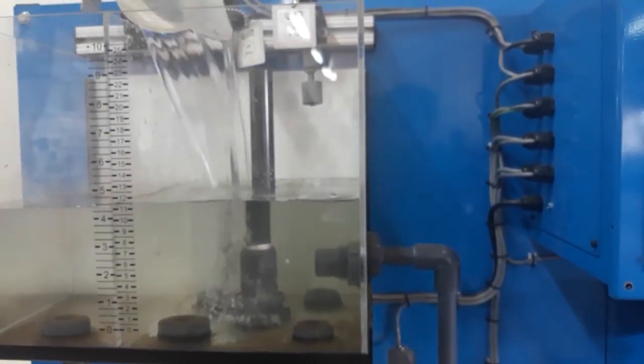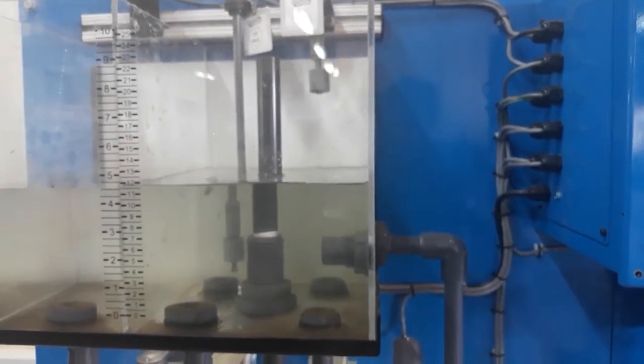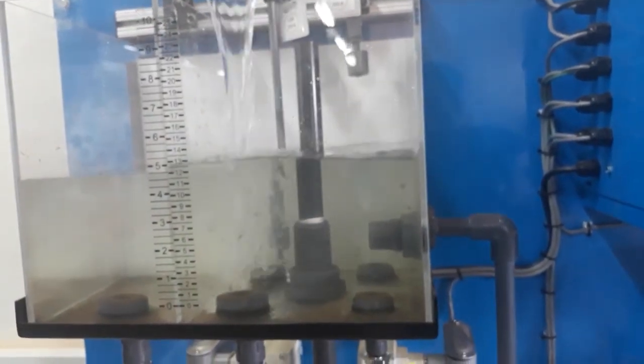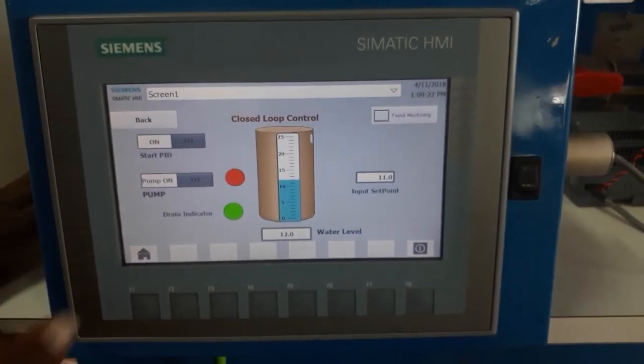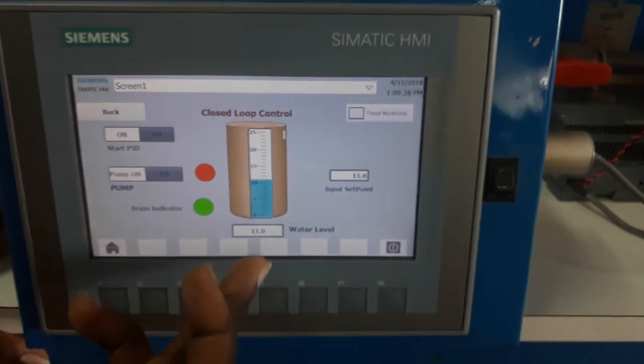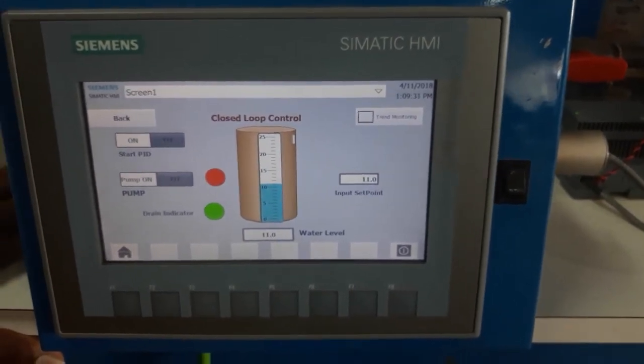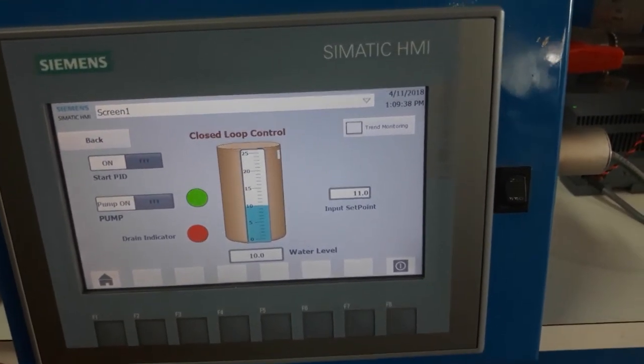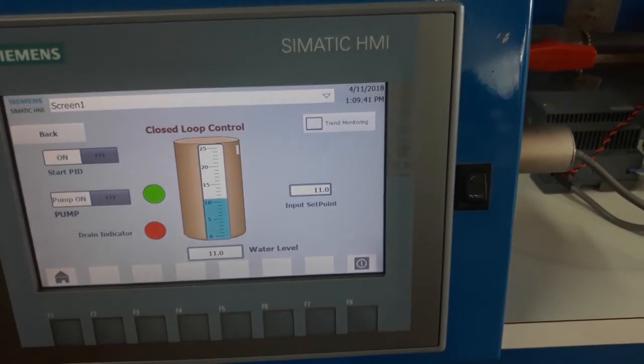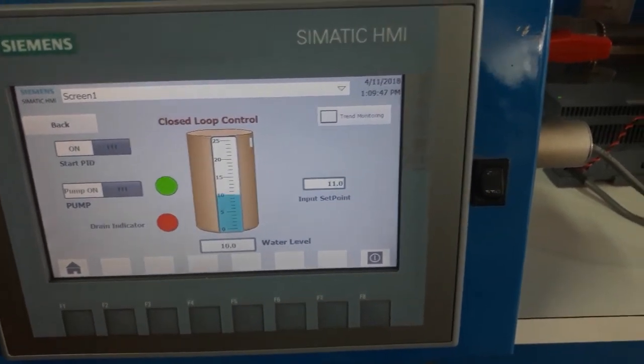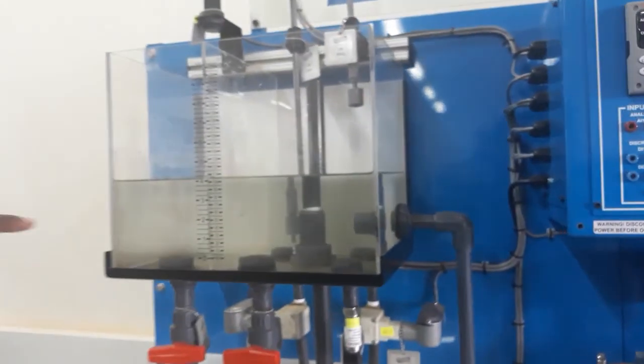Now, you remember that the setpoint is still at 11. We are trying to see the behavior of the system. As you can see now, the sound which was emitting from the motor is off, and the drain indicator is green, indicating that the system has detected that the water level has surpassed the setpoint by the predetermined value, and it is trying to reduce the water level to the original setpoint, which it has successfully achieved, and the motor has just come on right now, since the setpoint has been achieved.